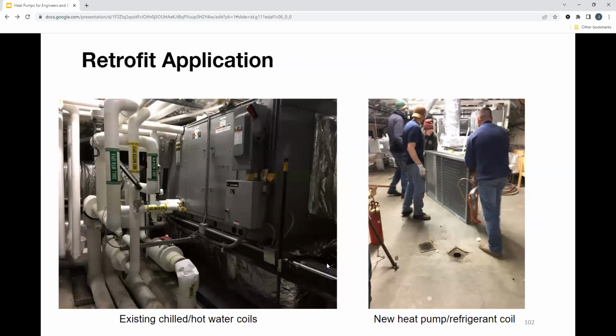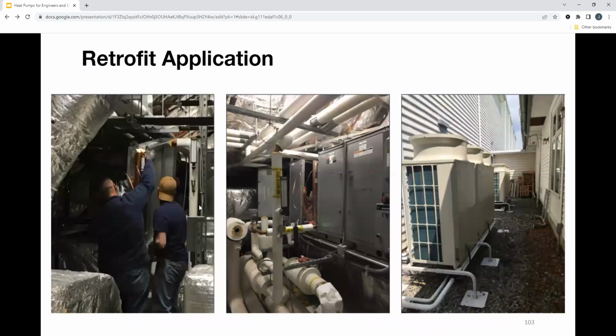Just showing you a retrofit application that's been done. As you can see, there's an air handling unit right here that has a lot of existing chilled water and hot water coils going to the coil, right? We brought our DX coil in. This is the contractors taking it out of the box, moving it up closer to where they need to install it. That is your refrigerant coil that will be connected to the heat pump. As you can see, these copper coils right here, that's where your linear expansion valves are placed, right? Contractors installing it completely removed the hot and chilled water that was existing. And then you have your heat pumps on the outside. So these heat pumps are feeding these coils for this application. Just a great way to reduce your greenhouse gas emissions using an efficient technology for cooling and heat.